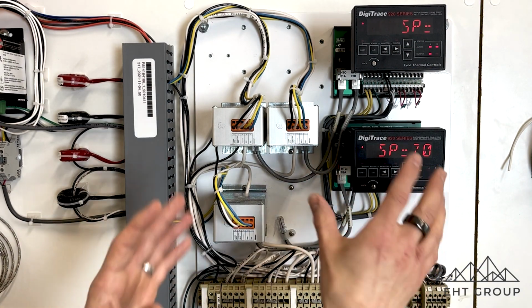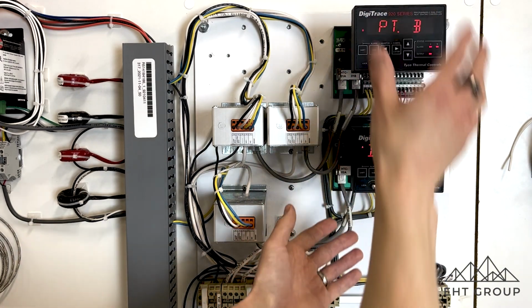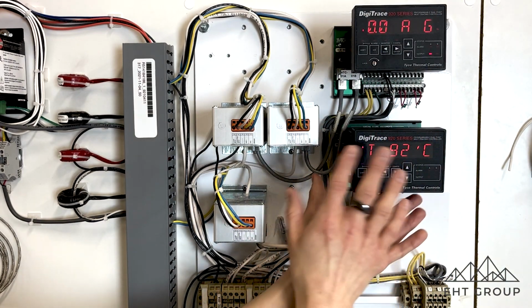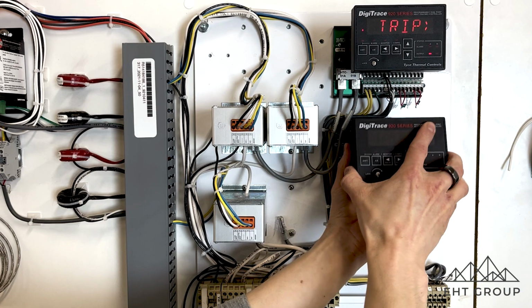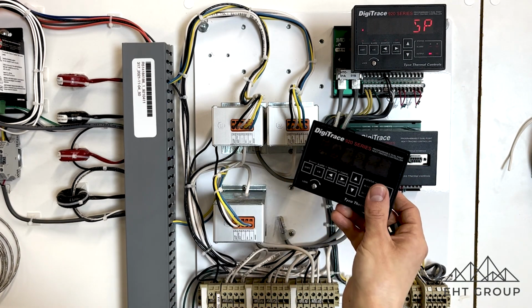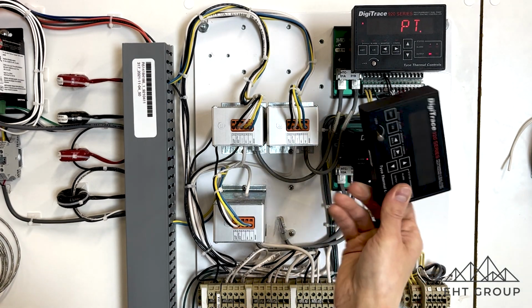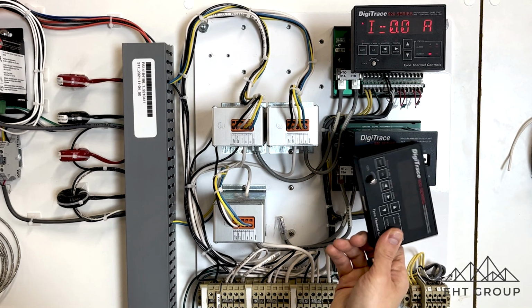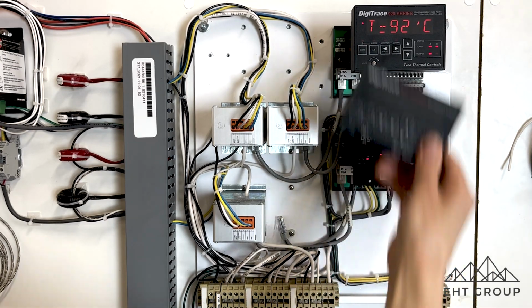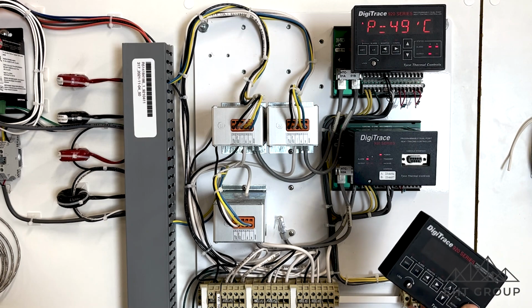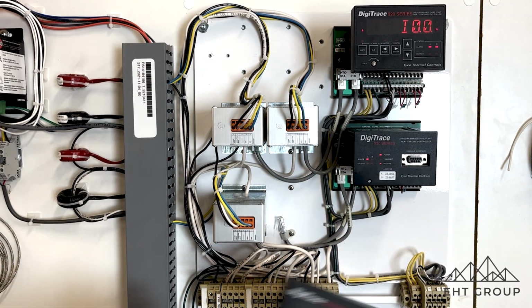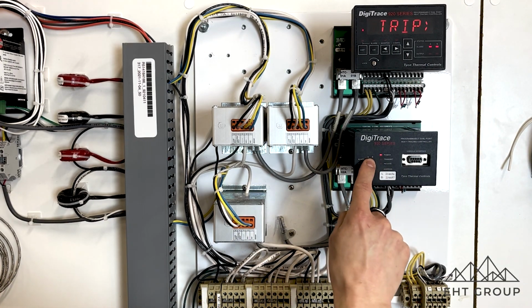The other thing on the actual heat trace controller is that there are a couple of components to it. I've already loosened all the screws in this module, but you have your interface module. Now, this is not the brains of the 920 heat trace controller, so this can come off and go between any other modules you have in your panel without any repercussions. This is the actual module itself.